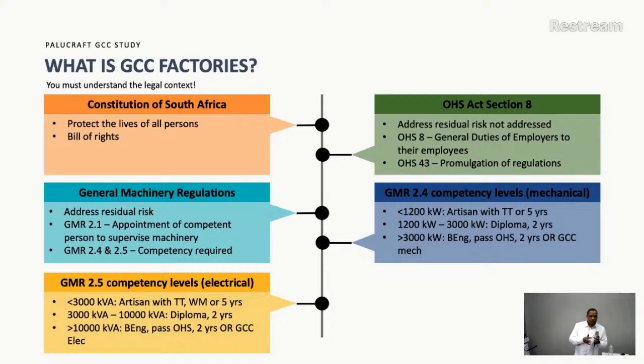Now when it comes to GMR 2.5, where it's for electricity distribution, the equipment I'm talking about there is most predominantly your transformers and your electrical equipment, such as your motors and your transmission lines, the cabling, and so forth. So if your premises has this electrical equipment used primarily or solely for distribution of electricity, then you need to appoint a competent person to supervise this machinery - i.e., you need to appoint a GMR 2.1. The competency of this GMR 2.1 will depend on the maximum demand that system is pushing.